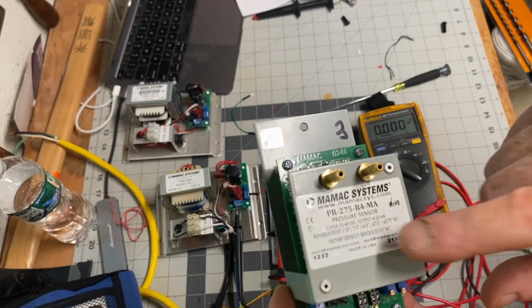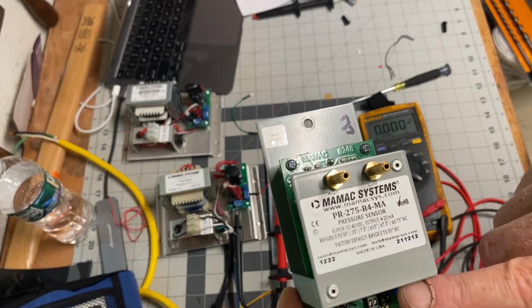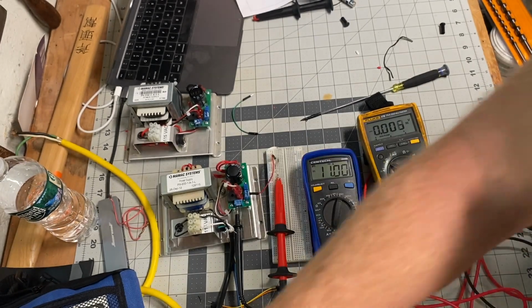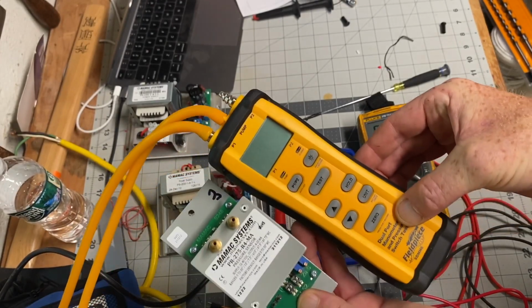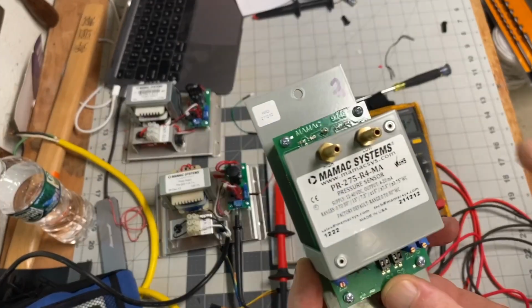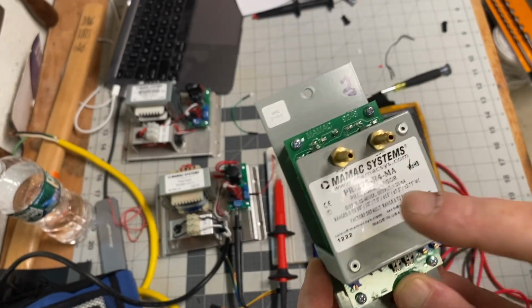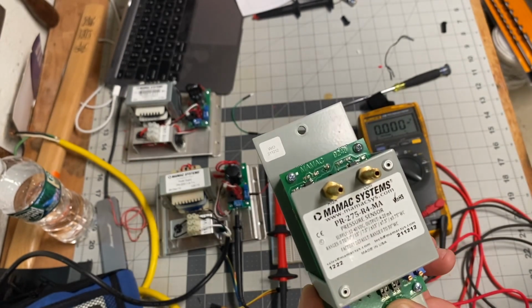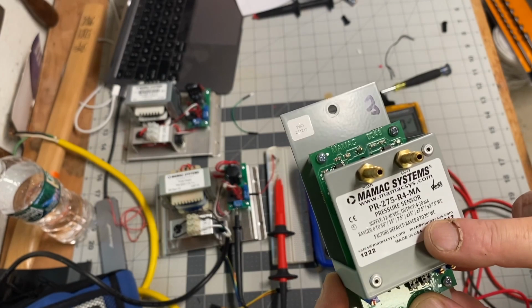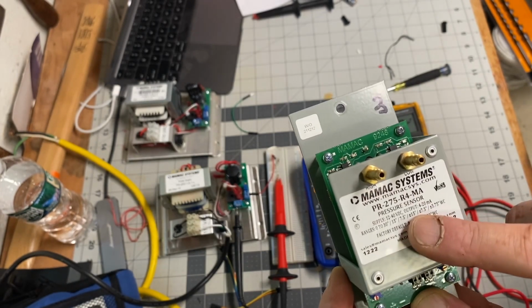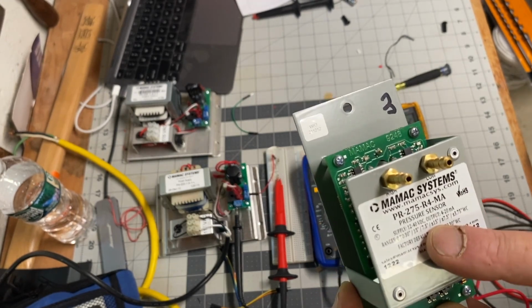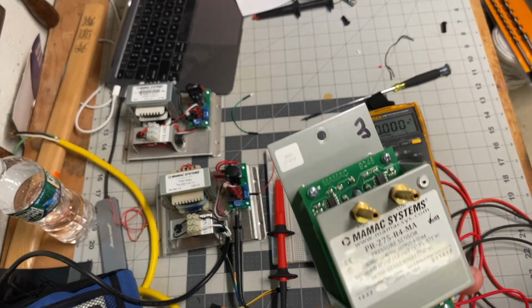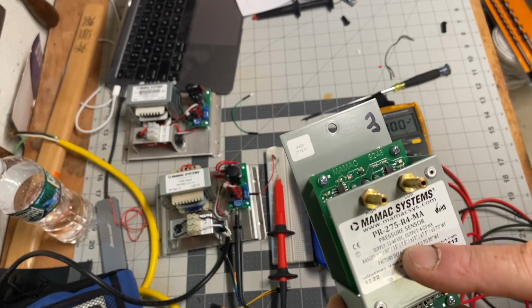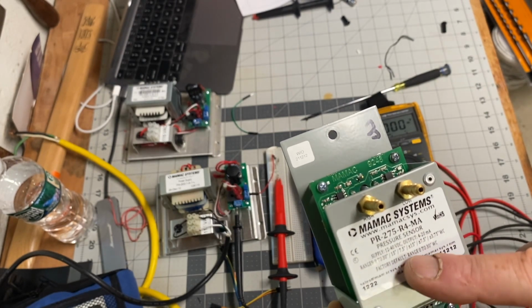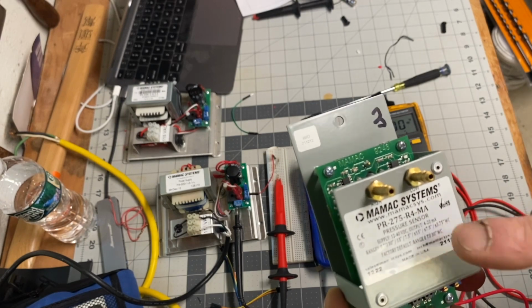And the calibration of these out of the factory has been horrible. So we had to go through and recalibrate them, using a pump like this, right? I'm able to simulate. We were running the range of 0 to 7.5 inches, and ramping, recalibrating these things. And brand new out of the box, we replaced a couple before trying to do the calibrations, and we found one that was spot on, dead on accurate. Running it with the pump through the full range, reading the milliamps. And then the other one out of the box was garbage. I didn't start to see a change in the milliamp reading until we got up to 2 inches. So you've got to be careful of these guys. But I'll do another video on the full calibration on these things.